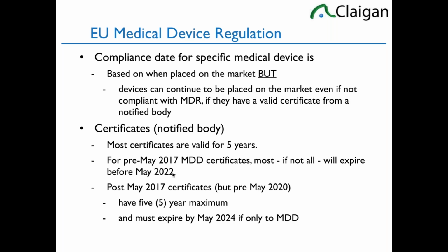The reason I'll explain the "more or less" is that it's a bit complicated. Normally, for CE marking directives, any item or unit placed on the market after the compliance deadline, in this case May 26, 2020, must be compliant with this regulation. So any medical device placed on the market after May 26, 2020 needs to be compliant with the MDR, except if you still have a valid MDD certificate from a notified body. If you have a valid certificate from a notified body that's still valid to MDD, you can continue to sell the product even though it is not compliant with MDR after May 2020.